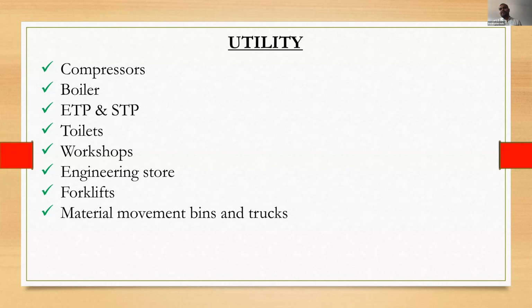Compressor should not load continuously. It will run 10 minutes and rest 5 minutes, meaning it goes idle, not that it stops. It's an automatic system, so it will stop load and then take load again. We have to maintain this continuously. If the rest time is less, it means the compressor is having huge load on it, which causes damage to the screws and bearings because of continuous running.